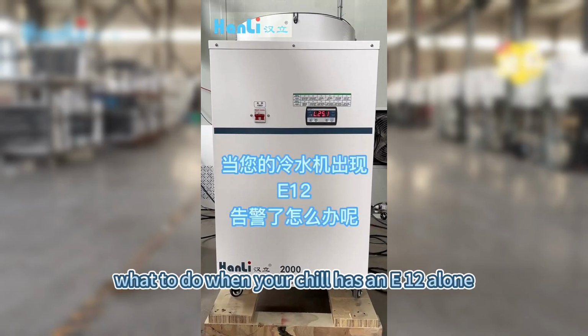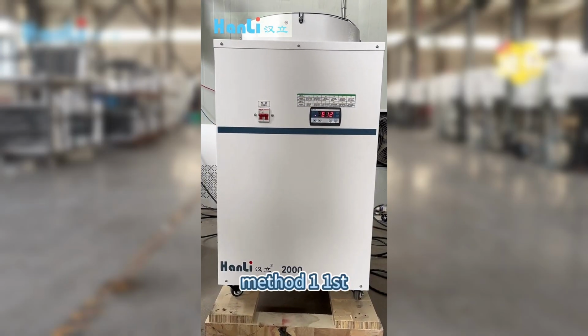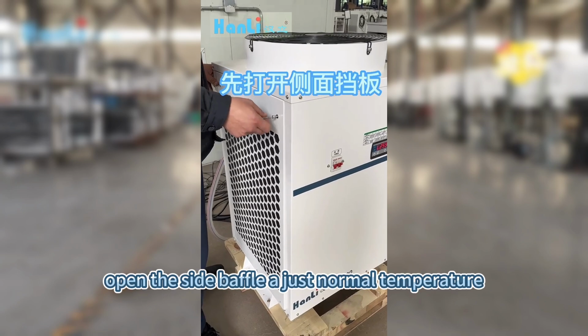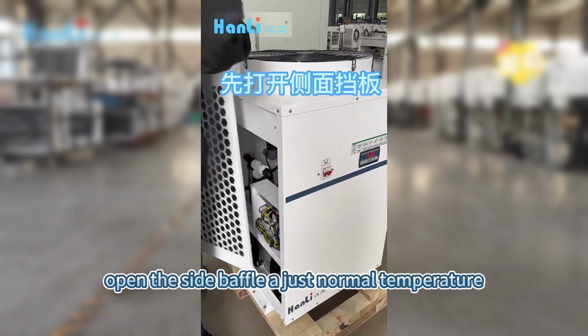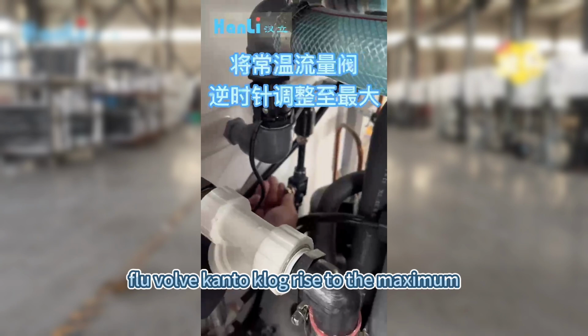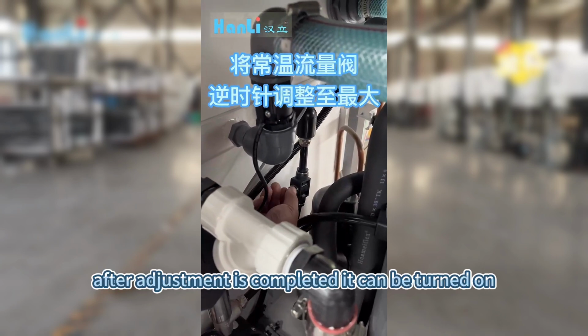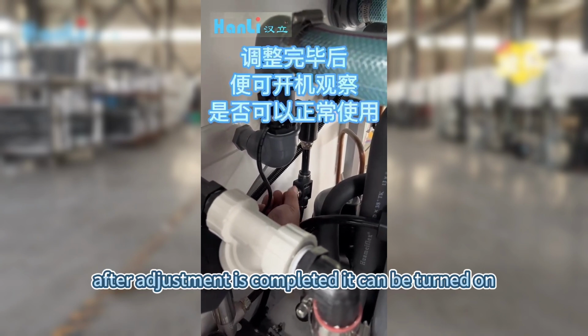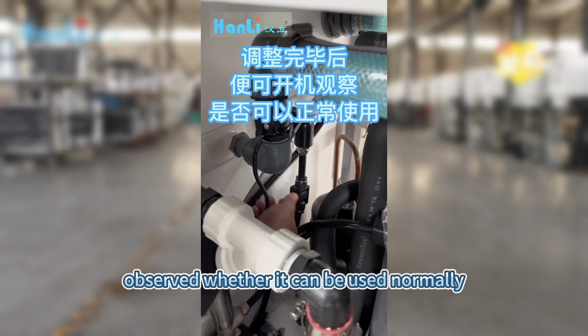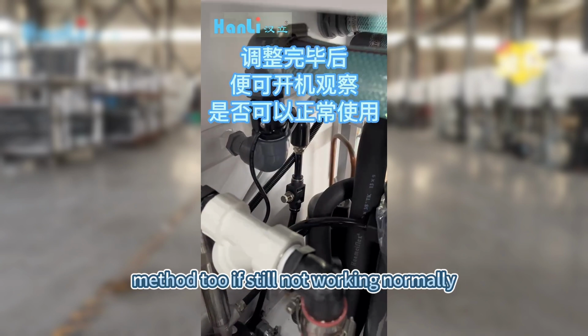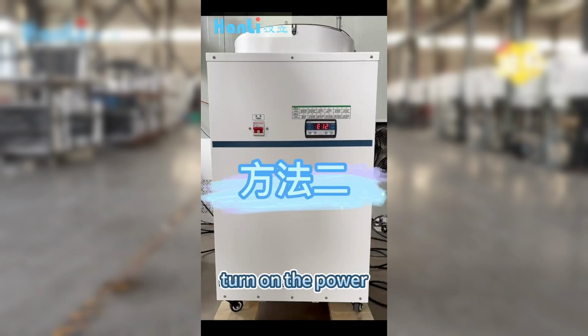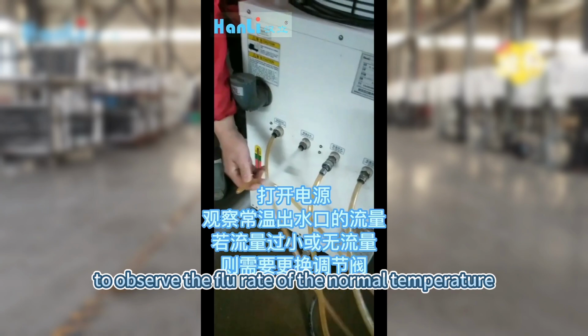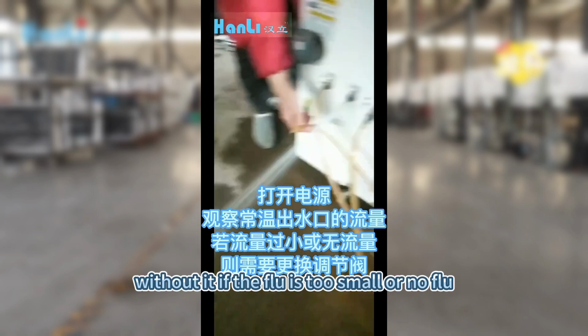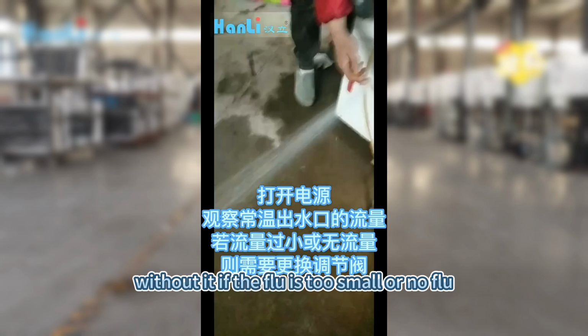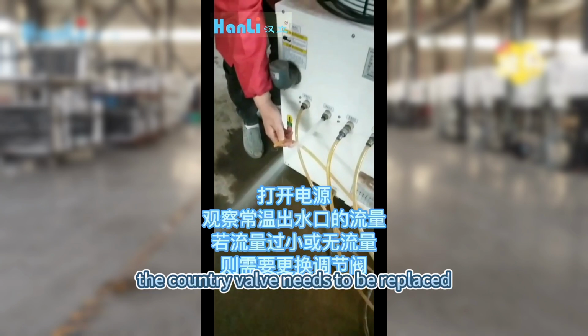What to do when your chiller has an E12 alarm? Method 1. First, open the side baffle. Adjust the normal temperature flow valve counterclockwise to the maximum. After adjustment is complete, it can be turned on. Observe whether it can be used normally. Method 2. If still not working normally, turn on the power to observe the flow rate of the normal temperature water outlet. If the flow is too small or no flow, the control valve needs to be replaced.